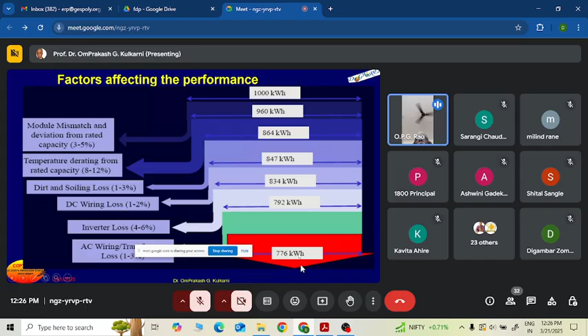This is one typical case I have considered. Then the inverter. Selection of the inverter is very important. It is not only the brand, but the quality of the inverter, the type of the inverter, and the technology of the inverter. You have to select it, adopt it, and install it correctly. If it is ignored, then you come down to 792 kWh. Then AC wiring, because again you are connecting it to the grid. That is ignored, again that loss adds to it, and say you are aiming at 1000 kWh, but you ended up with 776. It means almost 25% you are losing.